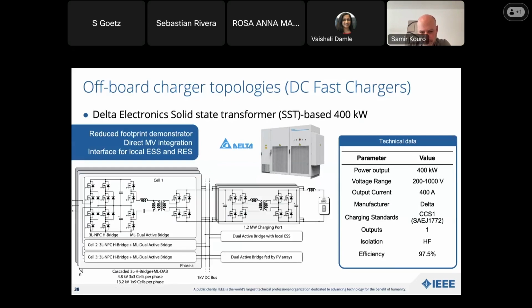And then finally, this is a demonstrator. I believe it's not commercial yet — maybe it is by now, but to the best of our knowledge this is a demonstrator in which Delta Electronics is proposing a solid state transformer rated at 400 kilowatts to not just connect a medium voltage DC or AC grid to the batteries, but also have flexibility to connect other energy storage systems and distributed generation plants like PV arrays, for more flexible operation.